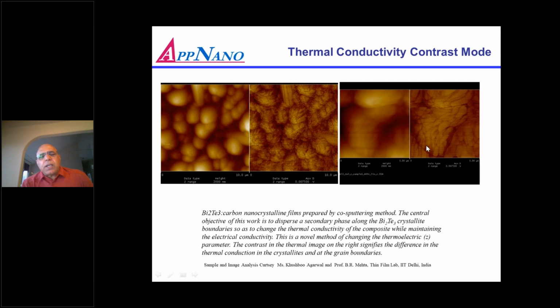Now these grains, I don't know if they're real grains or if this is because of topography, but the thermocouple is very sensitive. Even if it's a nanometer, the temperature change is huge. So you will see the grains in the thermal image better than in topography. In topography the tip cannot penetrate inside those grains, so you cannot see clearly, but you can see those grains very clearly in the SThM mode. So this is one of the thermal conductivity contrast modes. There are further studies, the researchers from India were working on it. I don't know whether they could resolve this and figure out whether this is a real grain or just topography.